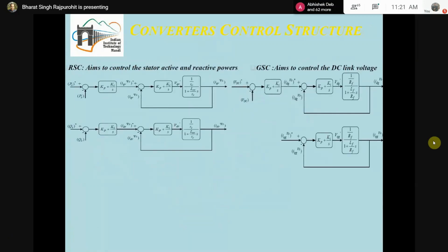These are the converter control schemes. I have already briefed them. The left hand side is for the rotor side converter. You can see there is a set point for active and reactive power. The active power set point comes from the maximum power point tracking algorithm. Then there are current control loops. On the right hand side, the grid side converter has the responsibility of maintaining the DC link voltage. That's why you can see Vdc reference is compared with the actual Vdc, and this current control loop is there. The grid side converter's lower control loop is for the reactive power.